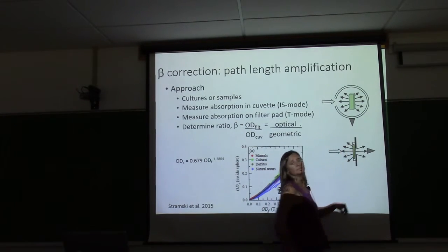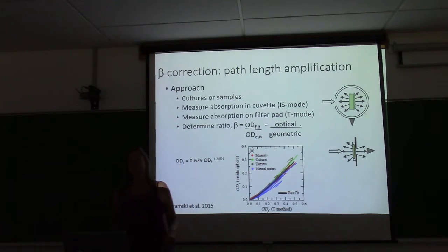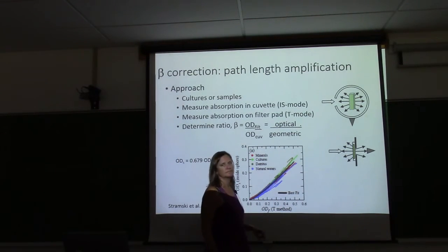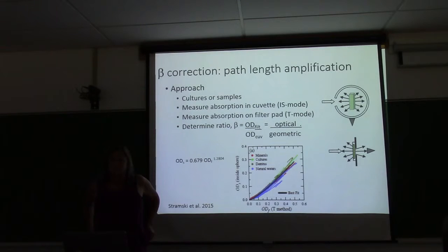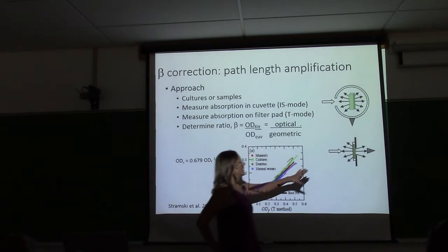So the beta correction for that versus the Cary 50 that you'll use tomorrow is going to be really different. Yep. So you need to have the type of spectrophotometer, the model, exactly how you place the filter. And so this whole idea of traceability, I think as a community, we have become a little bit more mature in terms of the importance of tracing what you may think is a trivial step, but actually becomes a really important component.